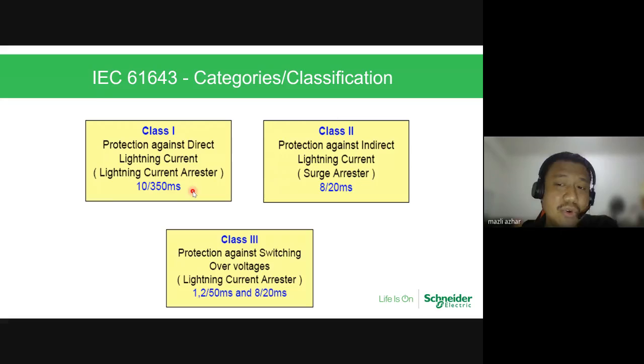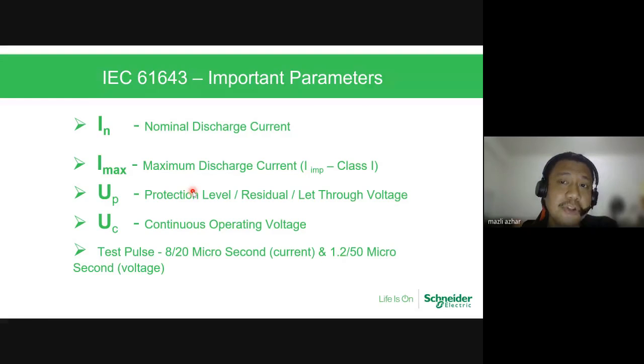When the class 2 for indirect, you don't have a lightning pole, but you are located near pylons or in a plains area or nearby to a high building. So the lightning will not strike your house, but it will strike the building, but the resonance created can travel to your house. So that's why you need to have a class 2. The important parameters, when you say an SPD, you will need a nominal discharge current, maximum discharge, protection level. This is where the SPD will start to operate, and continuous operating voltage, and then the test pulse.